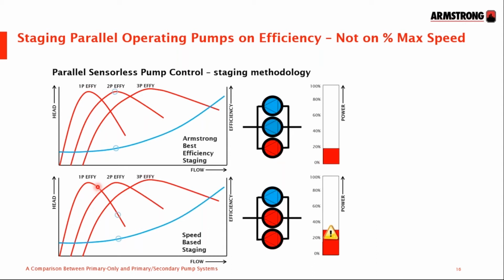The challenge with speed-based staging is that you're running the pumps through a large part of their operating load, both at low efficiency and high efficiency. Armstrong developed, a few years back, and patented the best efficiency staging method. We know the performance of the pumps, so we program in the maps and the best efficiency point of the pumps, so that at this point in the operating spectrum, rather than have one pump running approaching its maximum speed, we'll already have engaged the second pump, and we're back onto best efficiency with two pumps running, absorbing less power than we have with a single pump running.